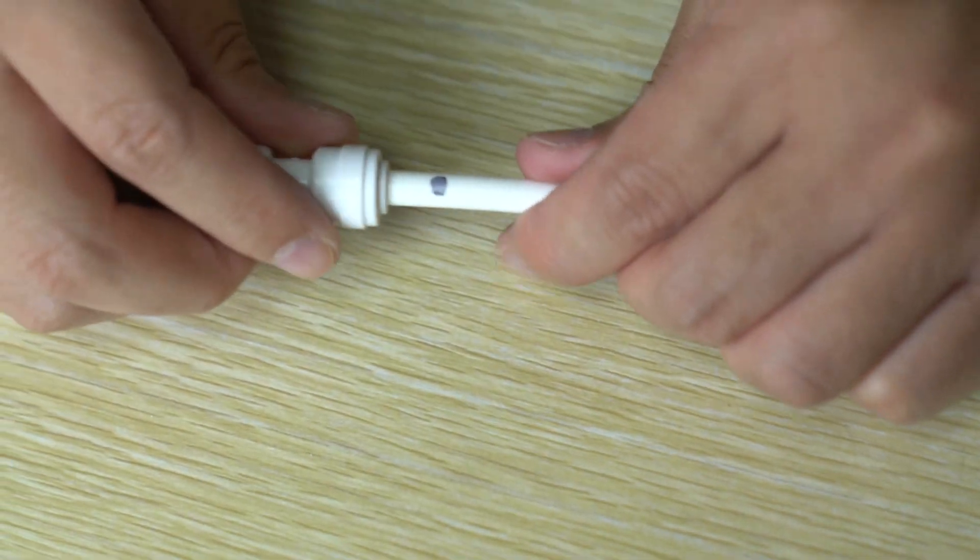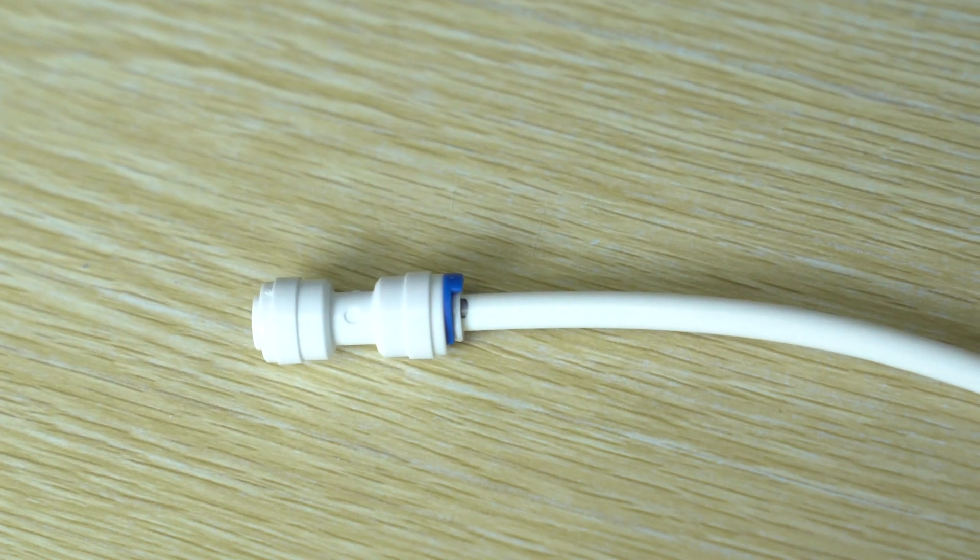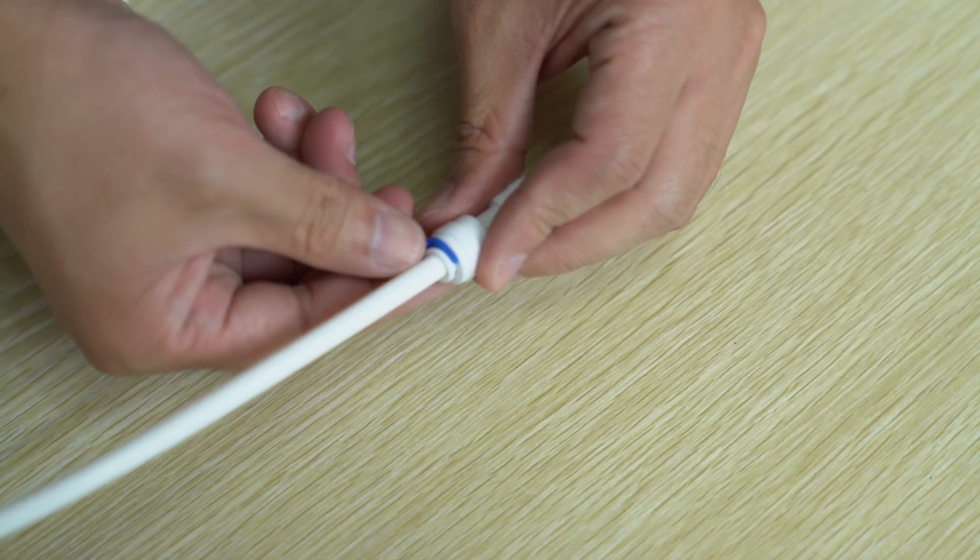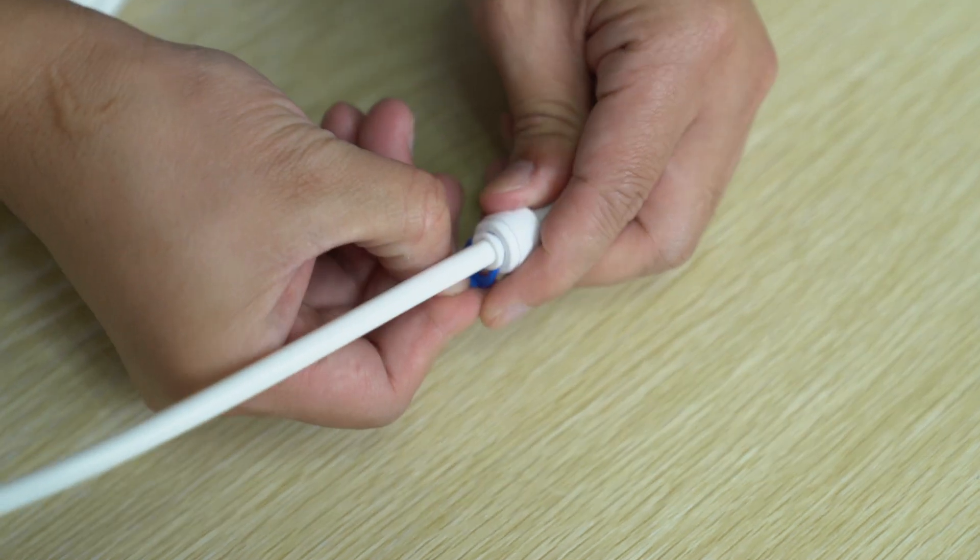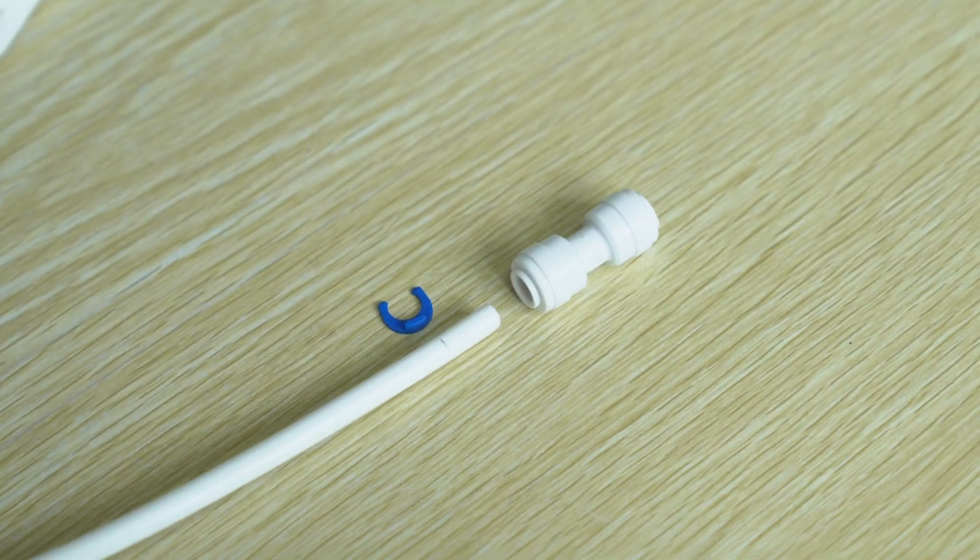When cutting the PE tube, use pipe cutters or a sharp knife, making sure you get a clean, square cut. To make sure the tube has been inserted correctly and to avoid any leaks, make a pen mark 5 eighths inch up from each end. That way you can tell if you inserted the tube fully into the Quick Connect fittings. To remove the tube, remove the locking clip and hold down the collar against the fitting and pull the tube in the opposite direction to release the grip.